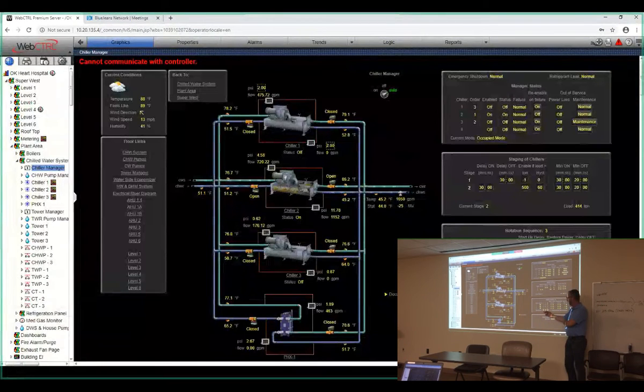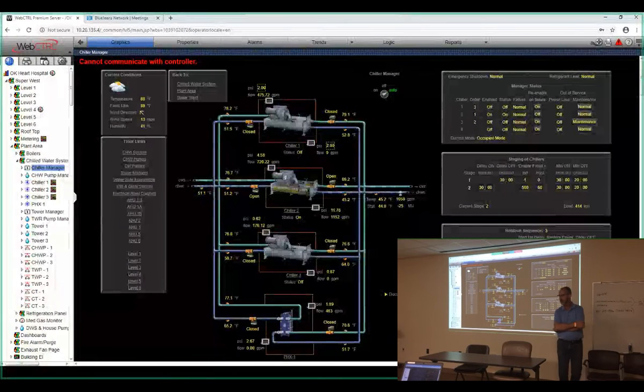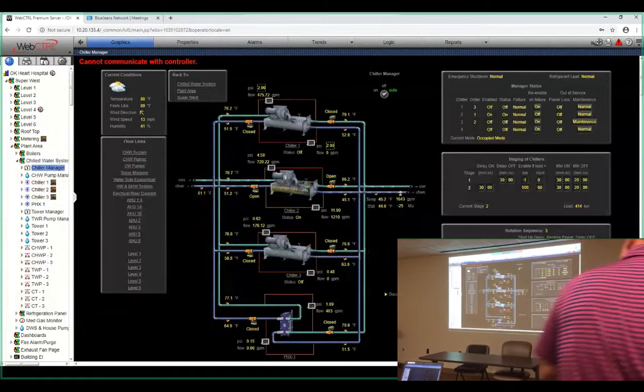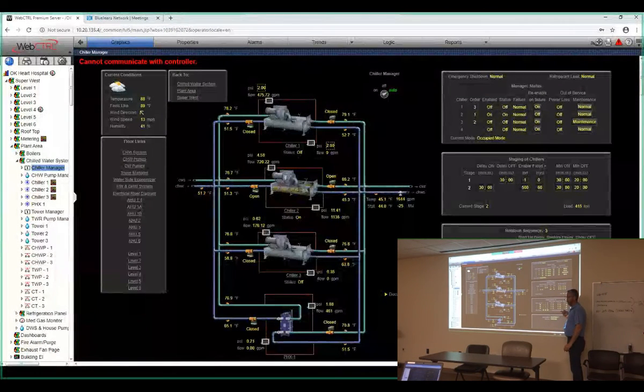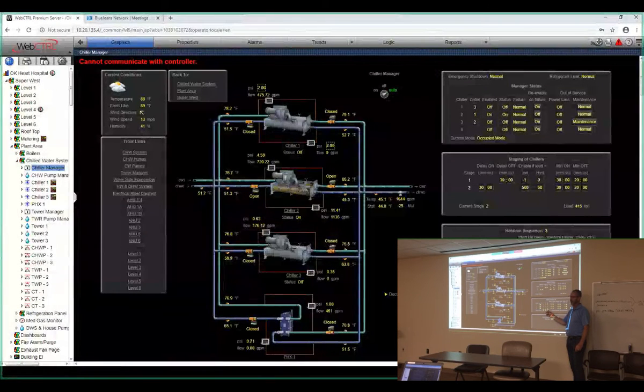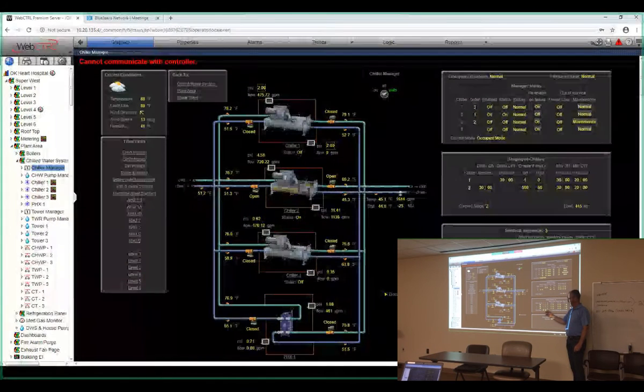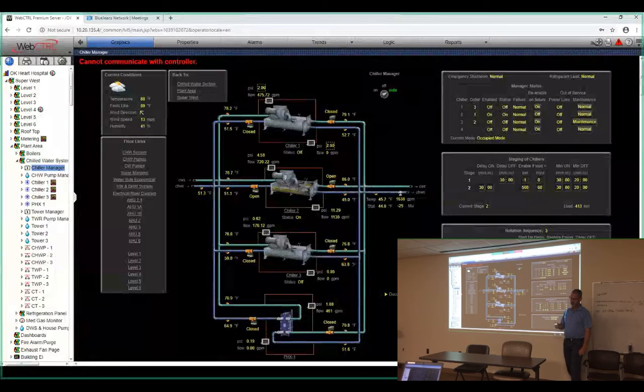Down here below is a manual selection, so you can force these chillers into any one of those sequences that you want to run. And the highest selected takes precedence. So if I select 1 and then turn on 3, this will be the sequence that I run in. These are manual overrides for you to use if you need to force it into a different rotation.